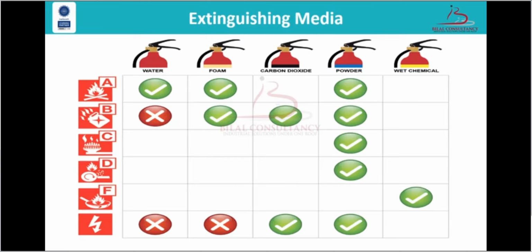Dry powder fire extinguisher. They are suitable for all classes including electrical fire with the exception of class F. They work by smothering the flames and may chemically interfere with the combustion process. They can be very messy and the powder must not be inhaled, so not recommended for use in confined space. There are special dry powders for use on class D fires.